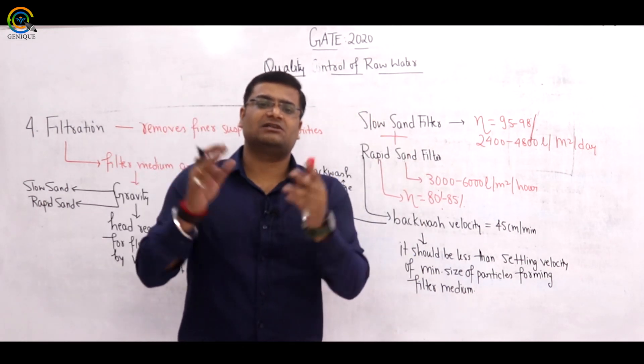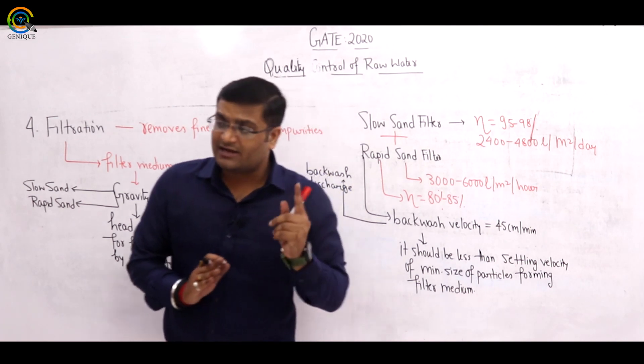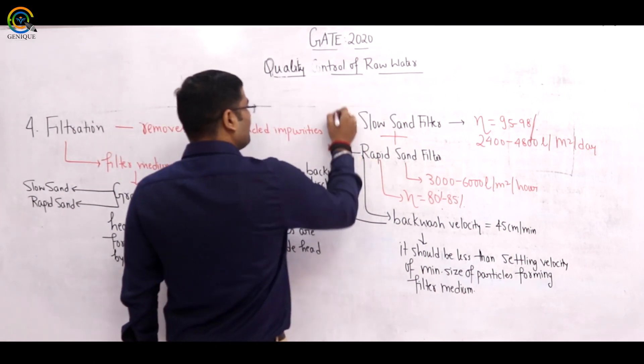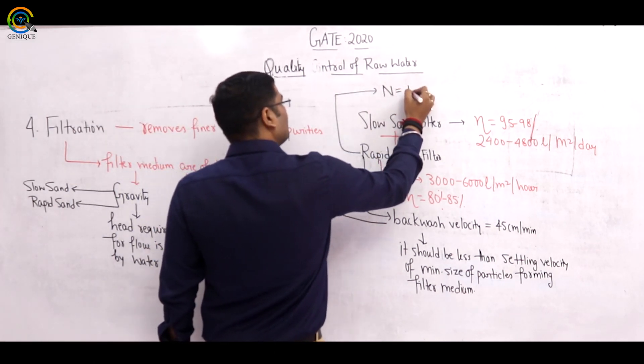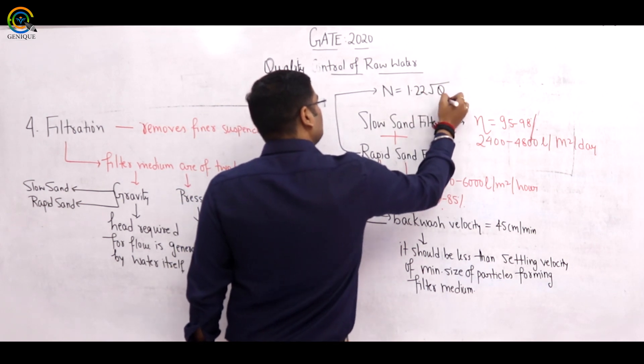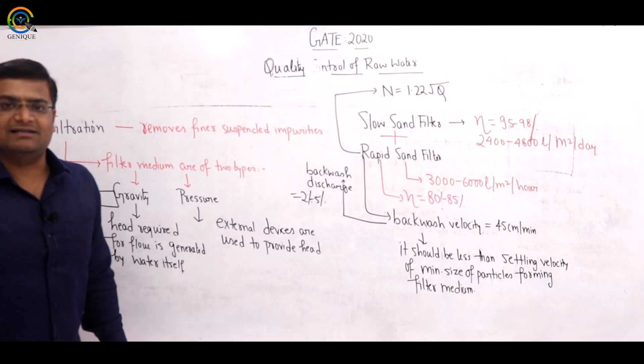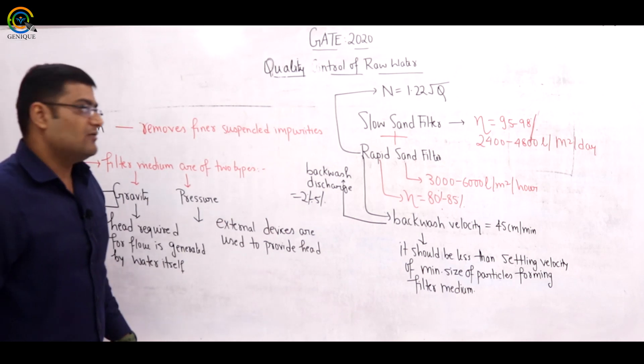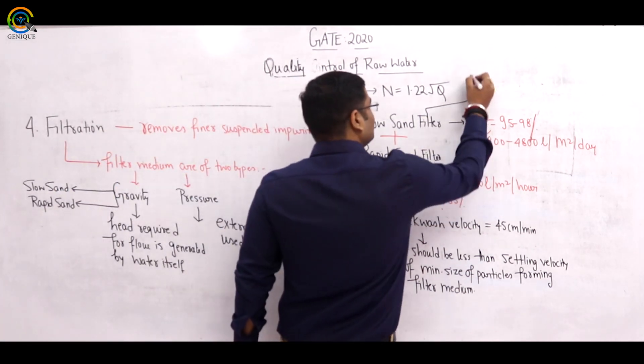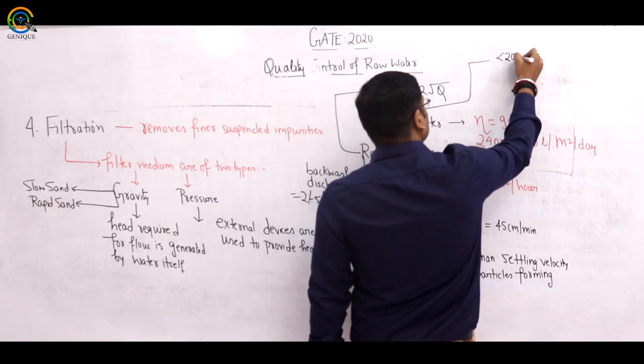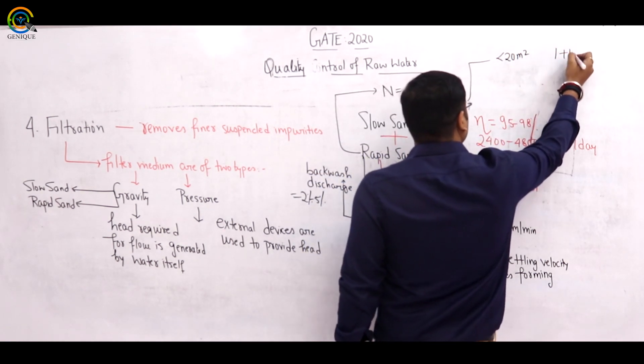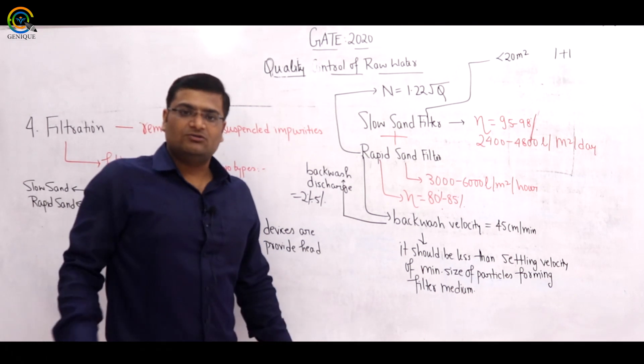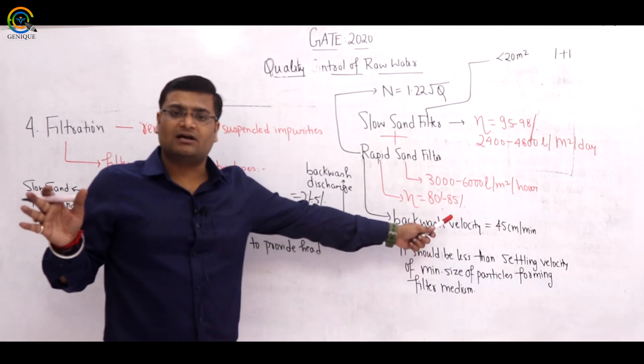Slow sand filter requires a larger area, whereas rapid sand filter requires less area. For rapid sand filter, the number of filters required is calculated by the formula: N = 1.22 × √Q, where Q is discharge in MLD (million liters per day). For slow sand filter, a standby filter is always kept additionally — if one filter is under cleaning or maintenance, the standby filter operates.